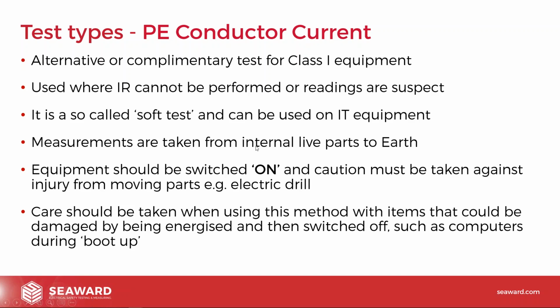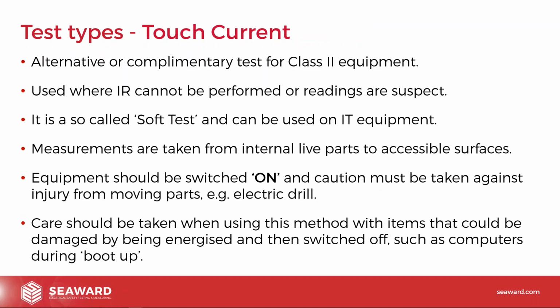So the protective conductor test is, as I say, another way we can check the insulation, but by applying the mains voltage to it. Touch current is very similar, and I think a lot of these bullet points are exactly the same as with a touch current test. But touch current is generally the test that we do on class 2 equipment, although it's not exclusively for class 2.